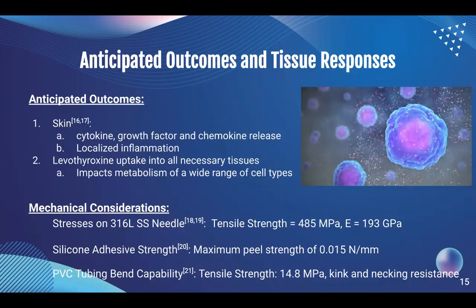For the mechanical considerations of our design, the needle would be a 20 gauge and about 20 millimeters in length. There has been risk associated with needle breakage at infusion sites for needles gauge 22 and above. Because we are using 316L stainless steel and a lower needle gauge, we do not anticipate breakage or corrosion in the body.